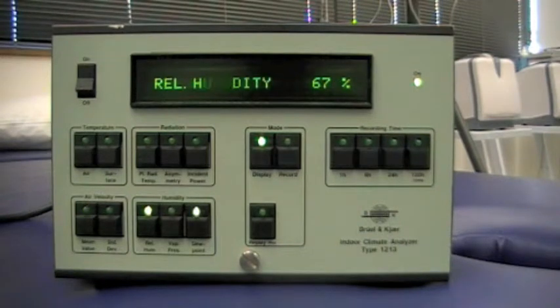The meter is now displaying the relative humidity at 67%. That's above the approximate comfort range of 40 to 60% that you might expect for an office environment.